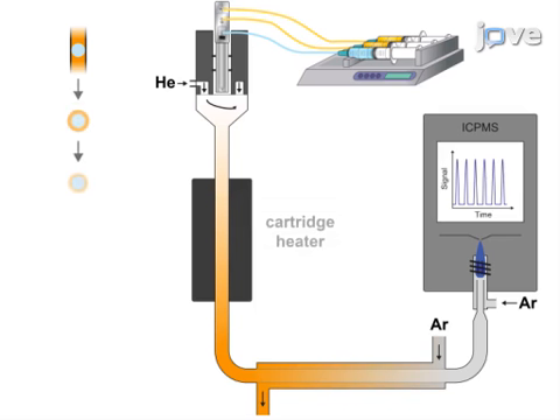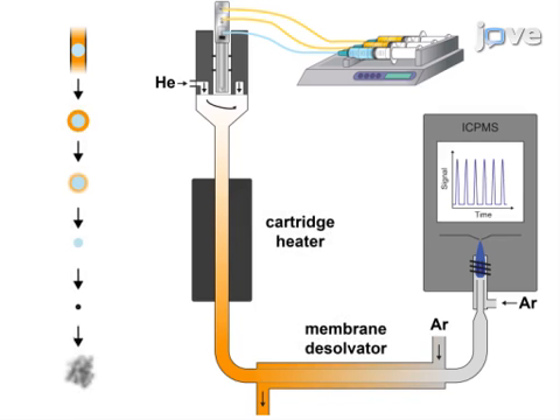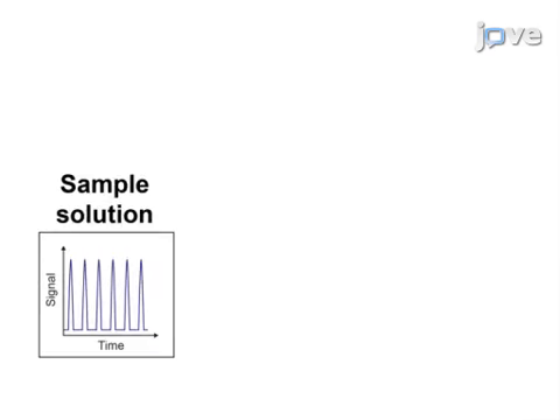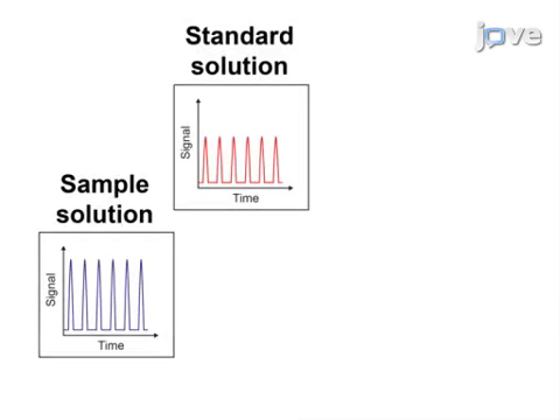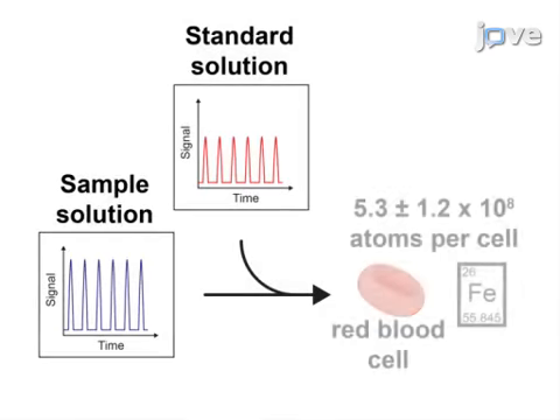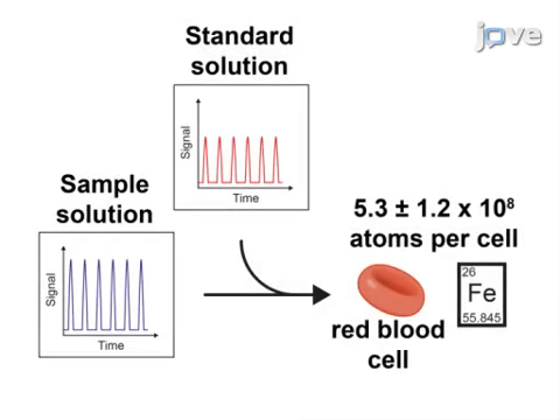The final step is to insert the chip into a transport assembly consisting of a cartridge heater that evaporates the droplets and a membrane desolvator that removes the solvents prior to the ionization and detection of the droplet content by an ICPMS. Ultimately, the recorded signals and a calibration measurement with a standard solution are used to determine the elemental composition of the sample solution or the cells in the suspension.